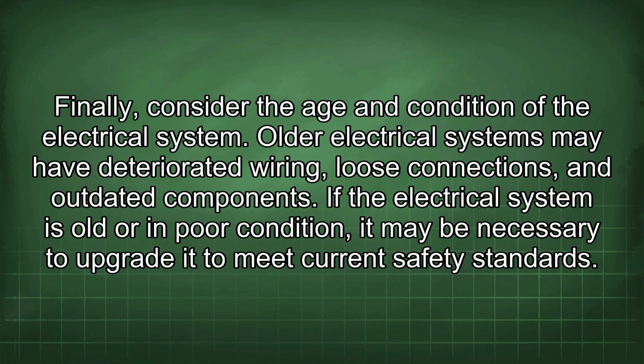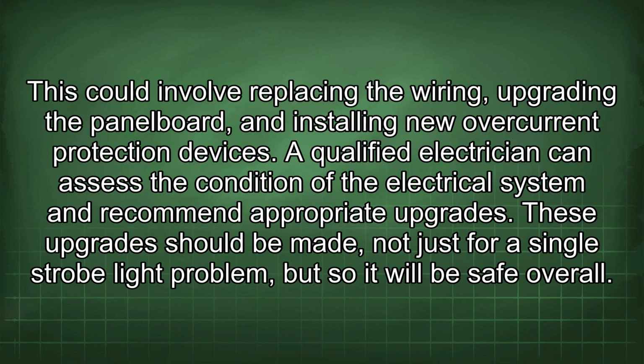Finally, consider the age and condition of the electrical system. Older electrical systems may have deteriorated wiring, loose connections, and outdated components. If the electrical system is old or in poor condition, it may be necessary to upgrade it to meet current safety standards. This could involve replacing the wiring, upgrading the panel board, and installing new overcurrent protection devices. A qualified electrician can assess the condition of the electrical system and recommend appropriate upgrades. These upgrades should be made not just for a single strobe light problem, but so it will be safe overall.